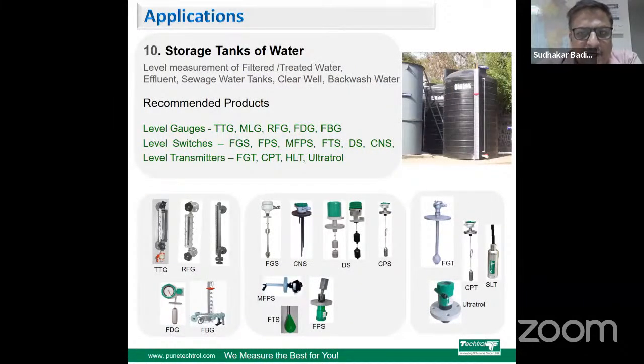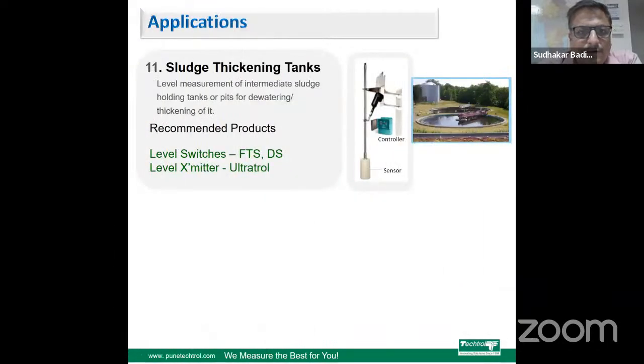Storage tanks are again a similar type. It depends on whether the tank is underground or overhead. We have both types of solutions, like float and dial gauge, and float and board gauge. Switches are also similar, such as conductivity and displacer, and level transmitters like float guided, capacitance, and hydrostatic. Same sonar for sludge thickening tanks.